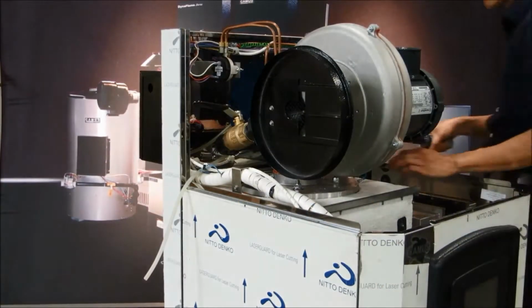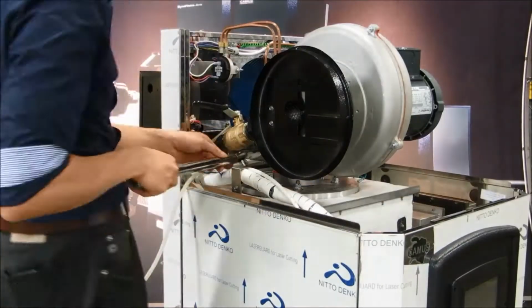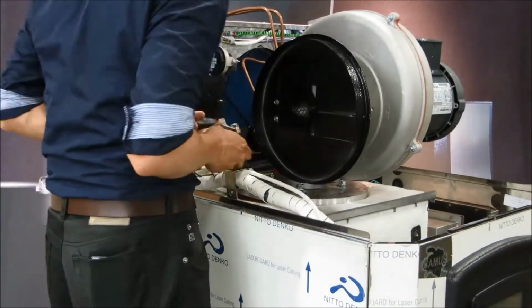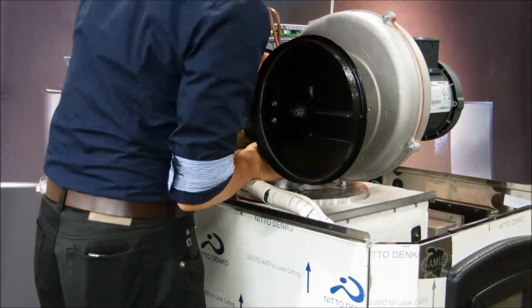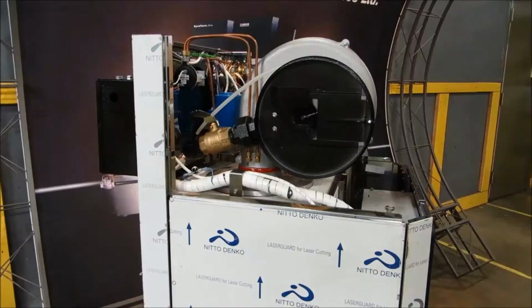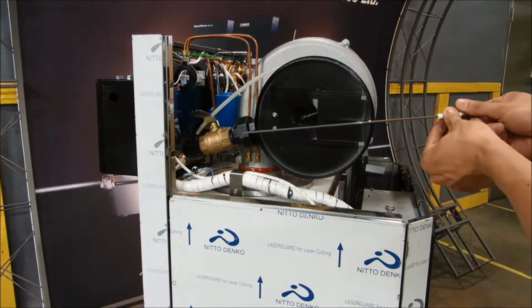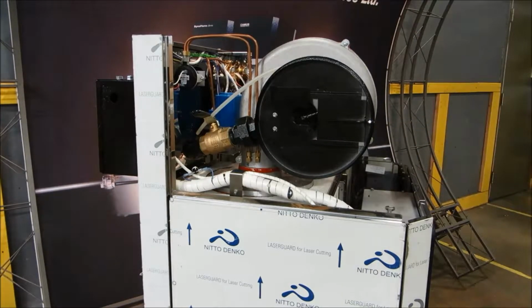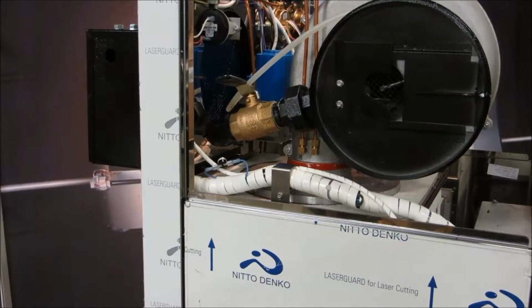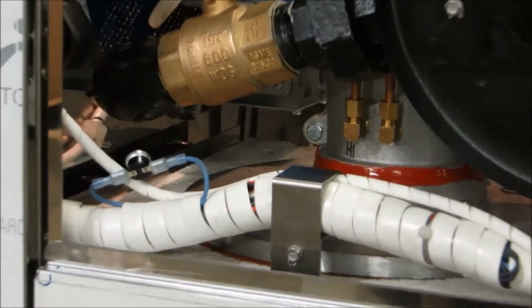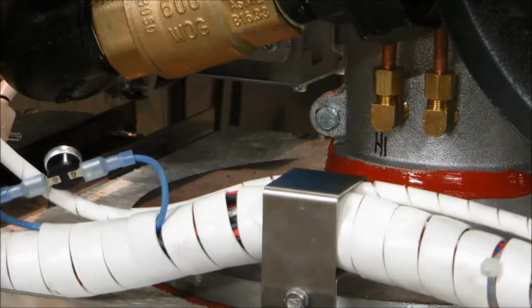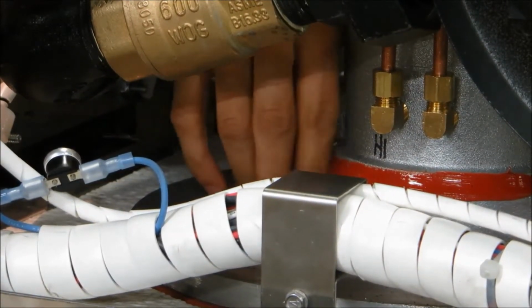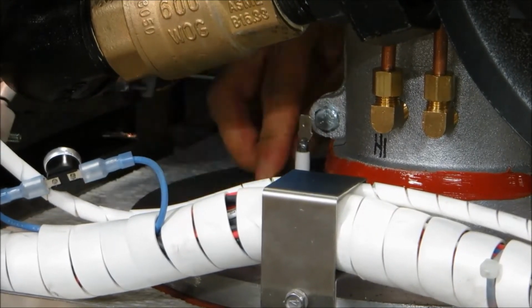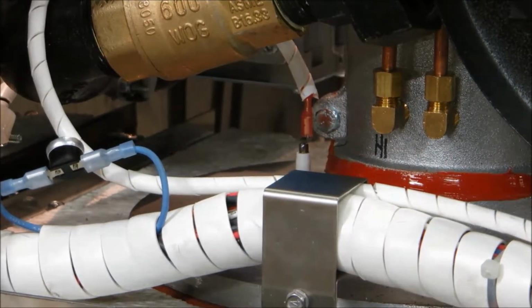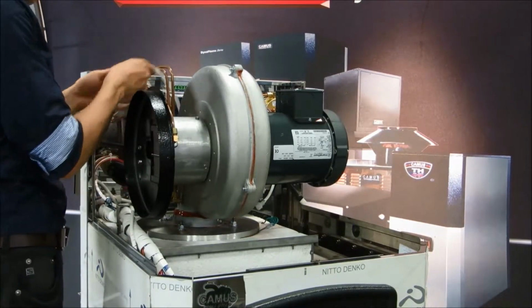The blower nuts must be torqued to 20 foot-pounds in a diagonal fashion so that the load is evenly distributed. Tighten the union on the gas train. Install the flame sensor and igniter. Reinstall the negative pressure feedback nylon hose on the aluminum casting.